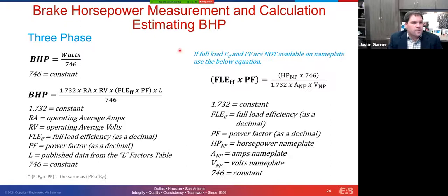All right. So we start talking about estimating brake horsepower in three-phase systems. I gave you this constant earlier, but brake horsepower is watts divided by 746. We talked about why that is, but this is the formula that we're gonna be using. And it's essentially 1.73, three-phase system. This is operating or running amps, running voltage. This is full load efficiency times power factor.